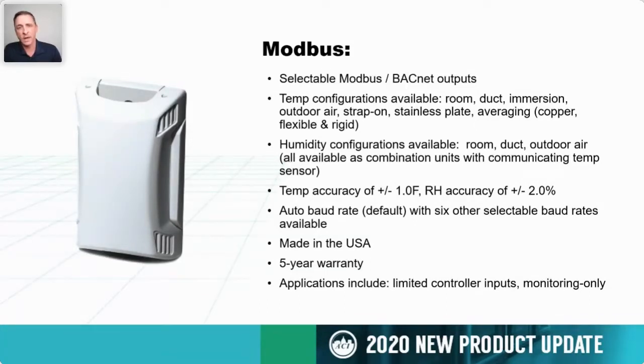We maintain a very high level of accuracy in these devices. It's plus or minus 1 degree F for the temperature and plus or minus 2% on the relative humidity side. Very easy to install and operate. They have an auto baud rate feature that automatically detects the baud rate, and a 5-year warranty. And we're seeing these being used in applications where you have a limited number of controller inputs, or you don't want to add another controller for one sensor, as a way to get a sensor on your network, temperature and/or humidity.